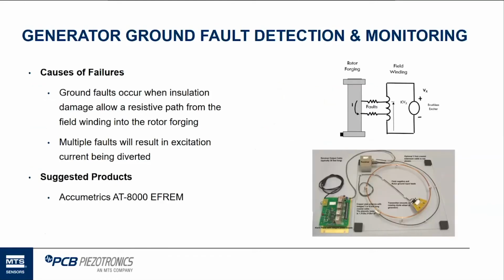So for generator and ground fault detection monitoring, we've got our ACCUMETRICS division providing a system looking at ground faults. They're caused possibly when insulation damage around the rotor or stator starts to wear out, and it starts to cause the winding to be exposed, causing rotor forging or other issues, and it causes that power within that unit current to be diverted.